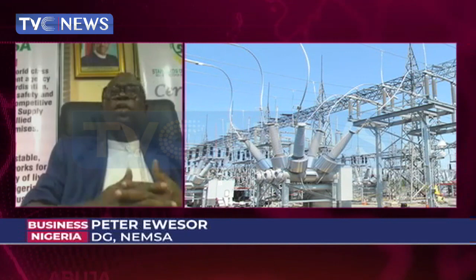First and foremost, we need standard construction and installation practice, so that the infrastructure put in place, from transmission to distribution, even to where the light enters houses, has been done in line with what regulation has specified. If you do not have adequate protection scheme... the rains are not supposed to deter us from having power if the network has been properly built, if the protection scheme has been properly graded, from transmission to distribution to even our houses.